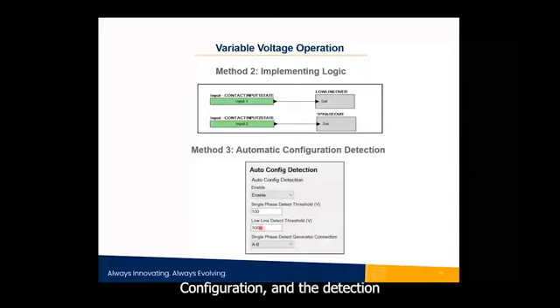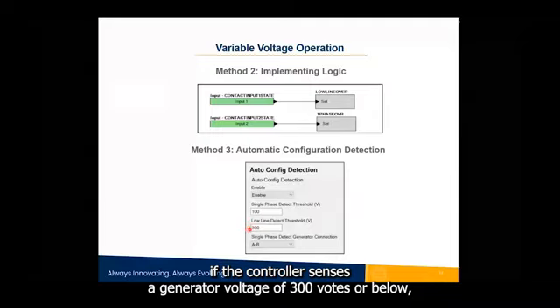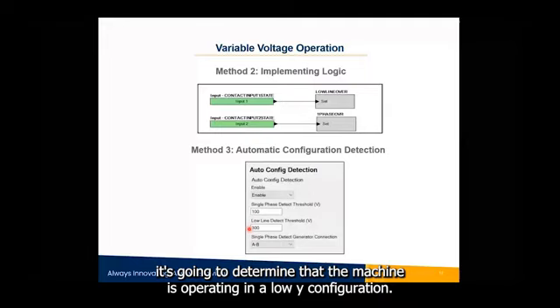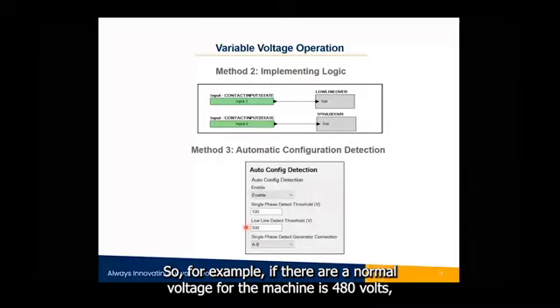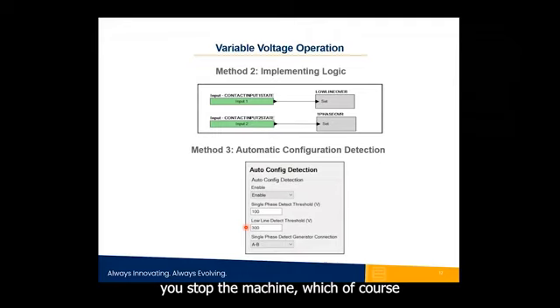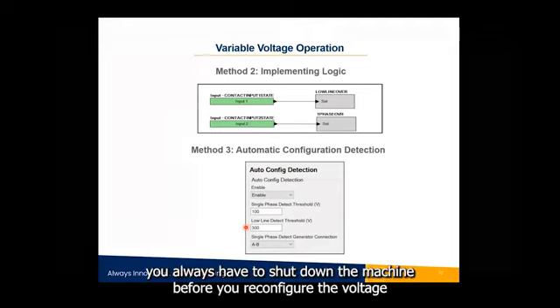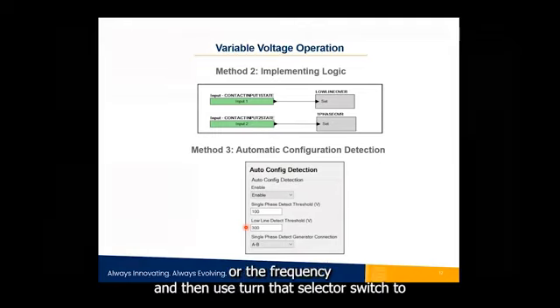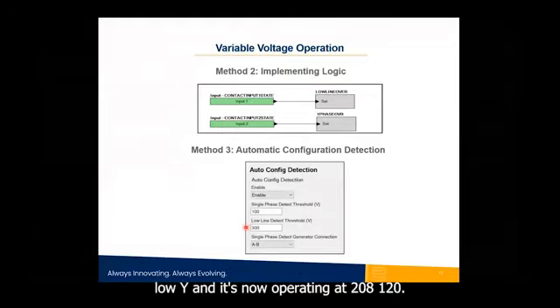And the detection threshold of 300 volts here means that if the controller senses a generator voltage of 300 volts or below, it's going to determine that the machine is operating in a low Y configuration. So for example, if the normal voltage for the machine is 480 volts, you stop the machine, which of course you always have to shut down before you reconfigure the voltage or the frequency. And then you turn that selector switch to low Y, and it's now operating at 208, 120.